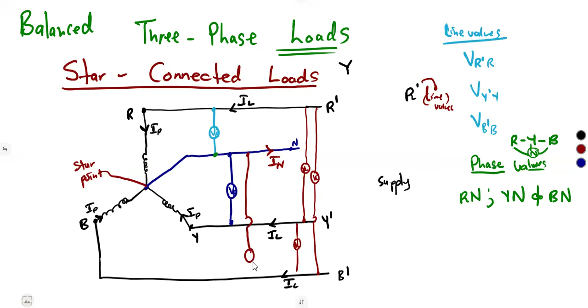Those are phase values. So it is the same here between yellow and the neutral. It's a phase value, this one. Yellow and neutral. The same thing from the neutral here, going to the blue. That value that you have there, it's a phase value because it's connected to the neutral. But from a line to a line, those are line values, right? So this is how you take your phase values.